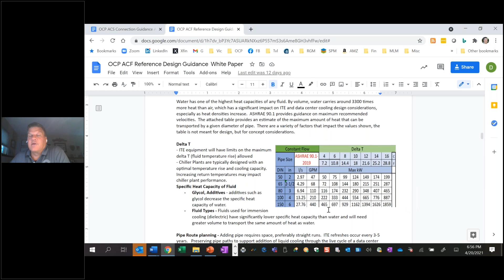One question that came up was, how big a pipe do you need? Well, that depends on how big a delta T and how big a KW you need. But for simplicity's sake, we used ASHRAE's flow limits. So the purpose of this drawing is to give people a feeling that if you're looking for, say, a megawatt of liquid heat, with a 10-degree delta T you could get close to that with, say, a 6-inch pipe, or 150 DN.